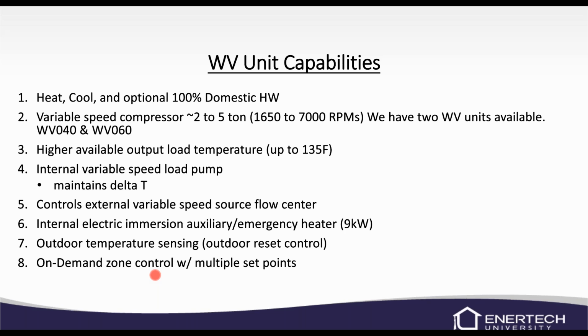Again, it is a variable speed compressor, and we have two units available, the 040 and the 060, so about a 3.5 ton and a 5 ton unit. The 040 will go from about 1.5 tons up to 3.5 tons, and then the variable speed 060 will range anywhere from 2 to 5 tons. Those are based on the RPMs. So it'll ramp that compressor down to about 1650 at the lowest, and usually about 6500, but it can go up to about 7000 RPMs on the high end.